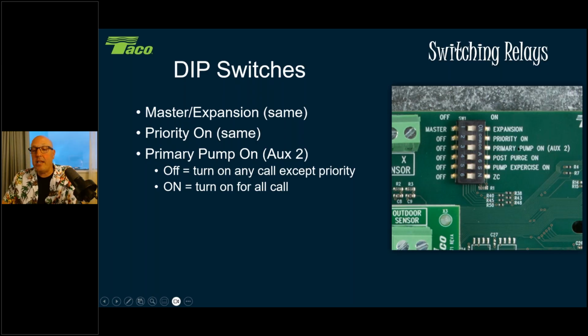Now, what we did here on the 3rd dip switch is controlling auxiliary 2. Auxiliary 2 is going to be my boiler pump. And if I have a wall-hung boiler that does not have an internal circulator, we need to control this. And we want to be able to turn it on or off for different applications depending on how you pipe it in there. For, say, your indirect tank, you might have your domestic hot water tank piped into the tappings right off of the boiler itself. And if you want priority, you got to make sure that pump stays off.